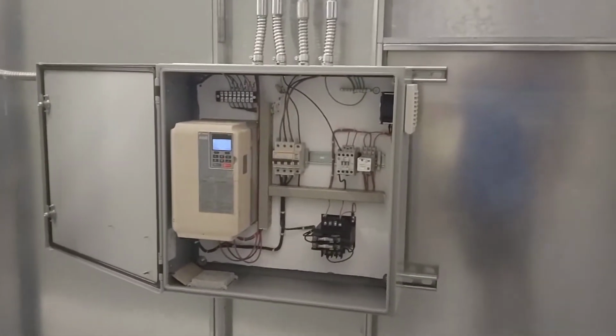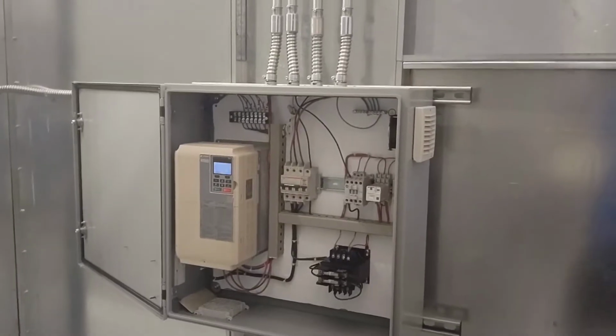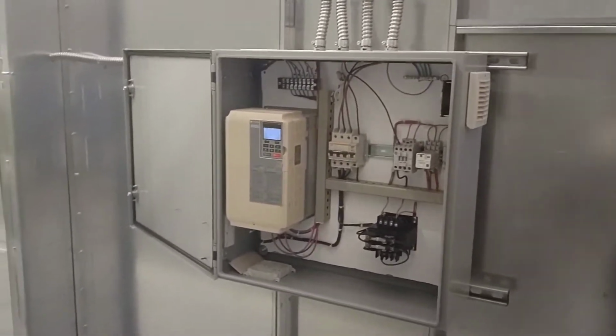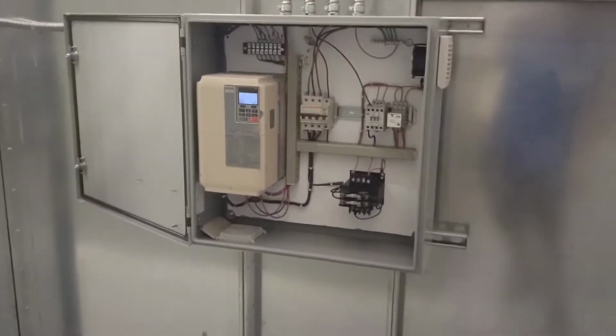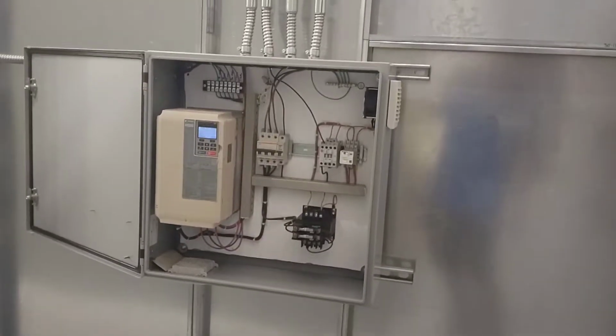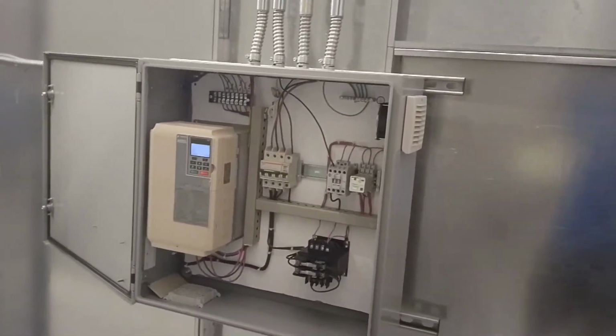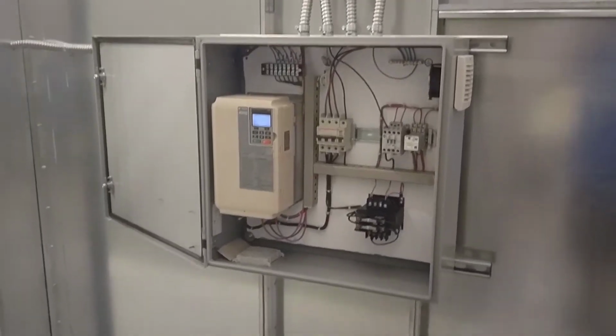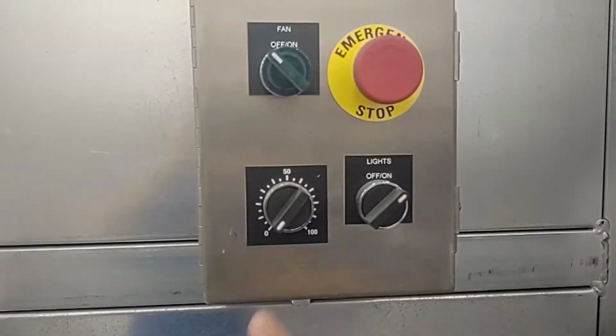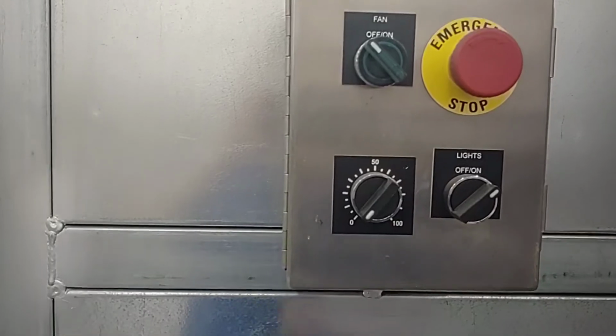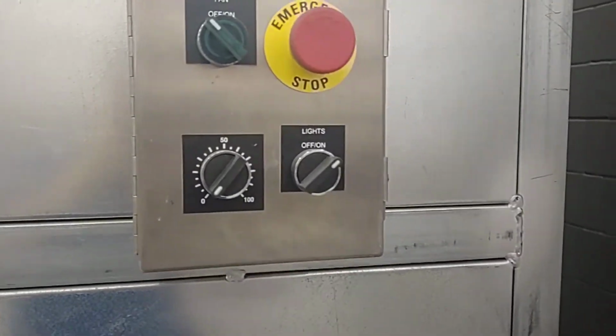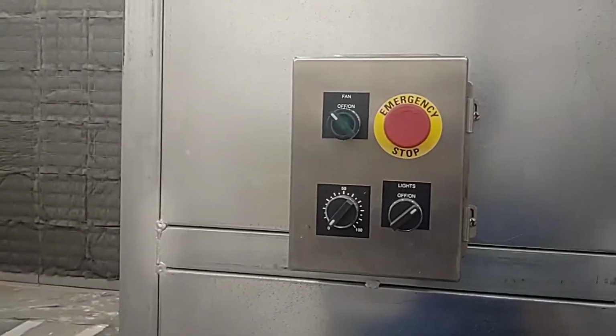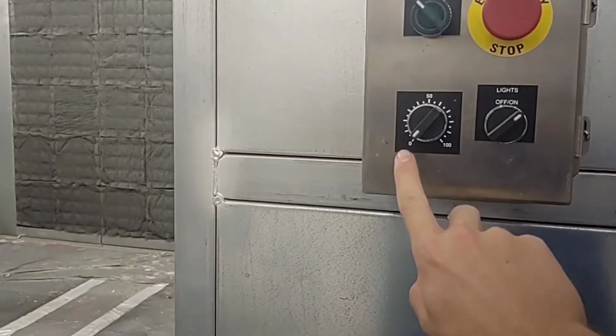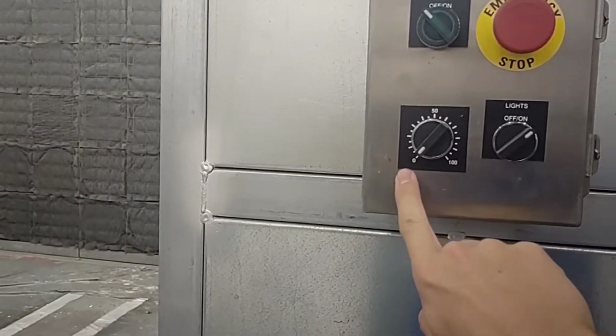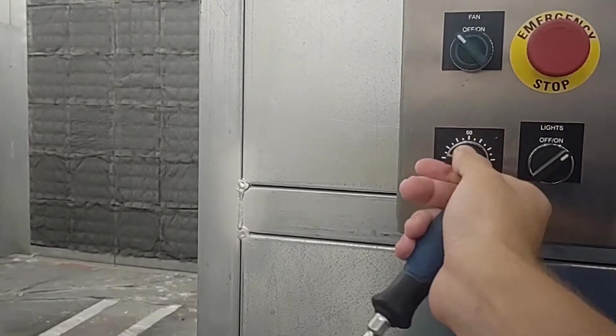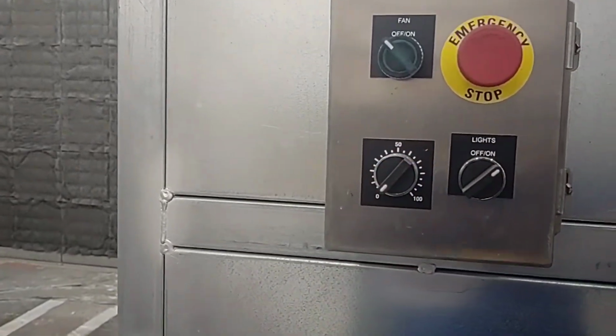So that's why we have a minimum speed set to 50%, which I think is more than enough to keep it running happy. Also, our motor is slightly oversized, so that also helps keep it a little bit cooler as well. And then we have the potentiometer here, which of course is going to allow us to control our speed. And the drive is doing all the calculations on making that not 0 to 100, but actually from 50% to 100. So this will allow us to go everything in between.